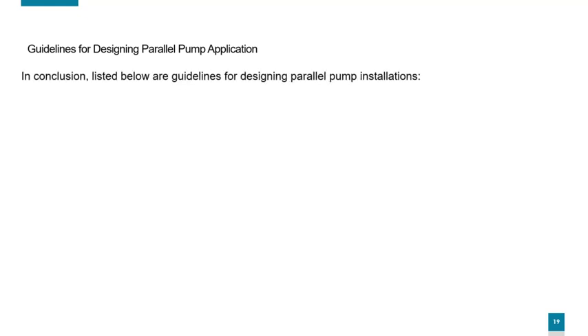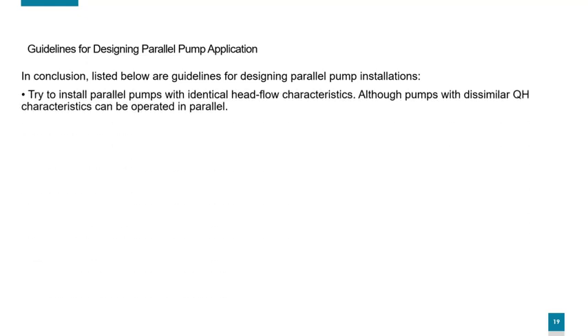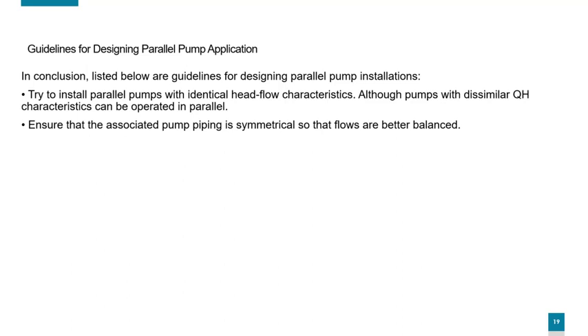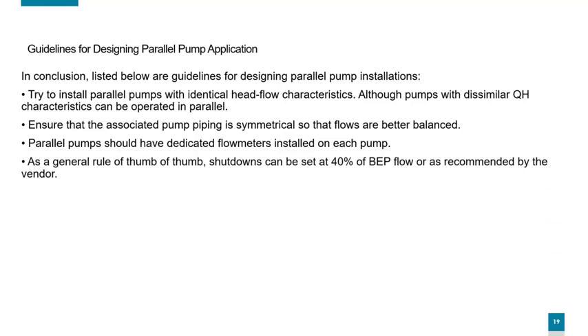Next, we have guidelines for designing parallel pump applications. In conclusion, listed below are guidelines for designing parallel pump installations. Try to install parallel pumps with identical head flow characteristics, although pumps with dissimilar QH characteristics can be operated in parallel. Ensure that associated pump piping is symmetrical so that flows are better balanced. Parallel pumps should have dedicated flow meters installed on each pump.